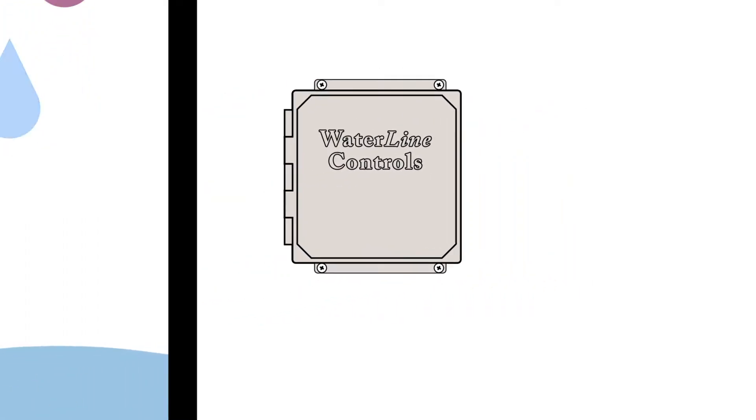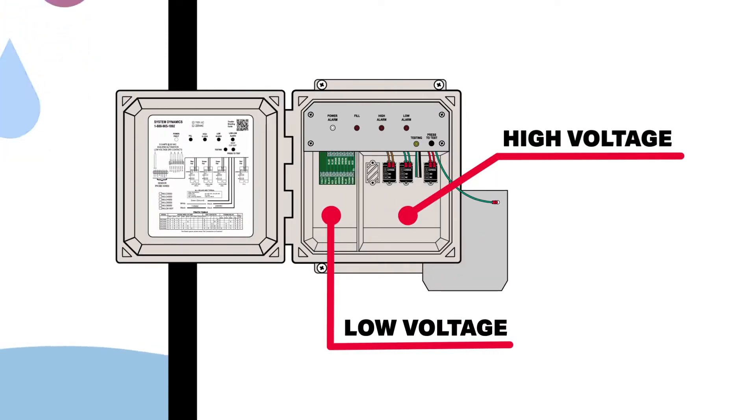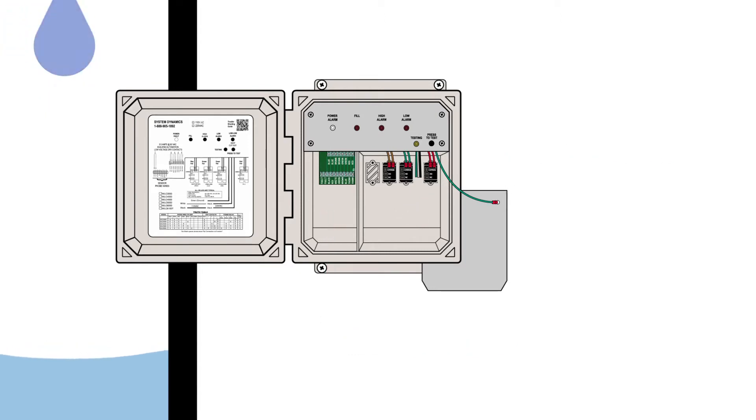When running metal conduit, keep note of the high voltage and low voltage compartments in the waterline panel. It's important to not cross high voltage conduit with low voltage conduit in order to avoid inductive electrical interference.